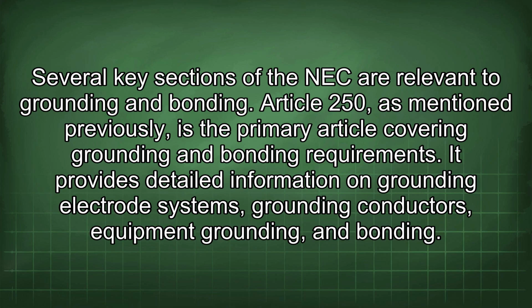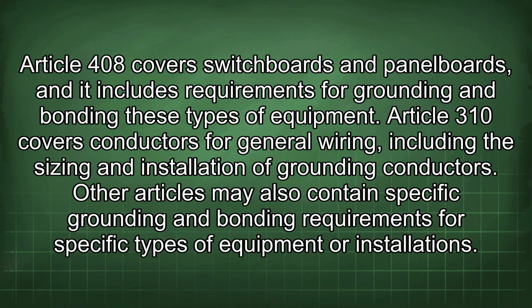Several key sections of the NEC are relevant to grounding and bonding. Article 250, as mentioned previously, is the primary article covering grounding and bonding requirements. It provides detailed information on grounding electrode systems, grounding conductors, equipment grounding, and bonding. Article 408 covers switchboards and panel boards, and it includes requirements for grounding and bonding these types of equipment.